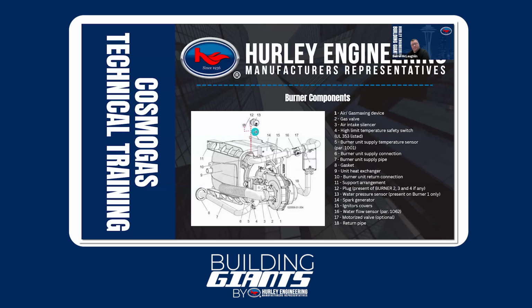On top, we've got a pressure sensor. So we also want to make sure they have an adequate amount of pressure. We're trying to guarantee that there are no air bubbles, no pockets. We're flooded and flowing at all times. And to do that, we have a pressure sensor. Now, if we have multiple boilers or multiple heat exchangers, excuse me, we'll only have one of these pressure switches. So we'll have one on our primary heat exchanger, and the rest of our heat exchangers will just have a plug.